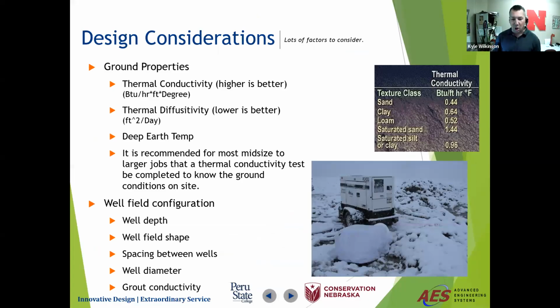Okay, here we were. More design considerations. So the ground temperature, which Vishal talked about earlier, is fairly constant around here, but we do have to measure it and see what it is so we can put that into the calculation program. Thermal conductivity is a measure of how well the ground essentially moves the energy, and thermal diffusivity is kind of the same type of thing. So we use those two values and the deep earth temp to help in the design calculations.